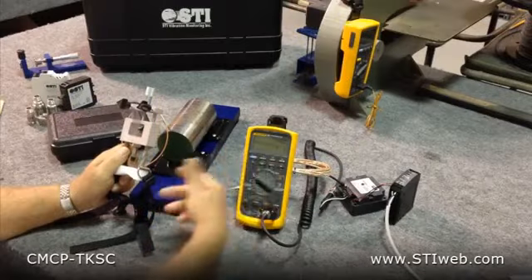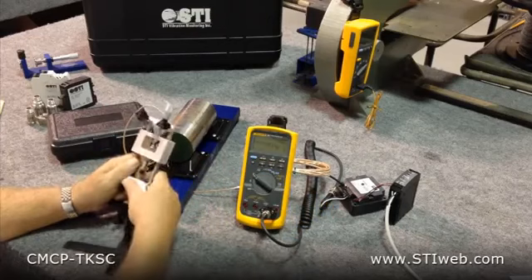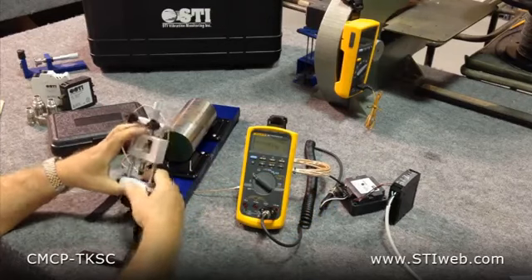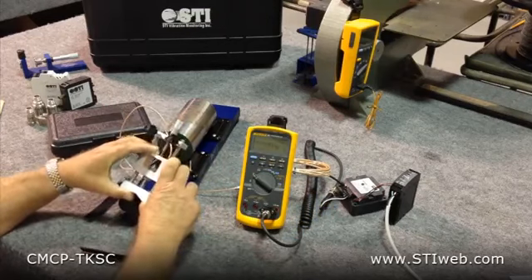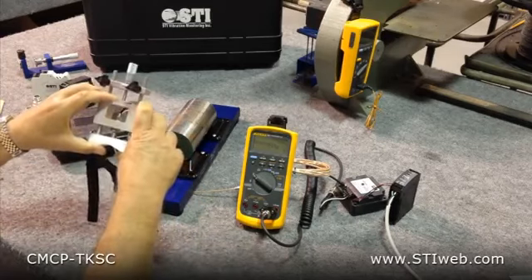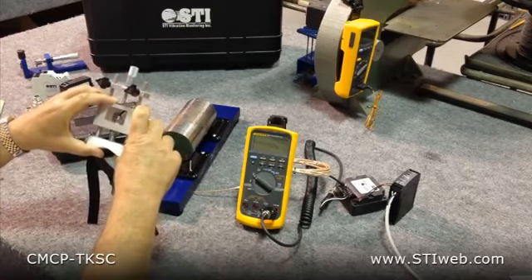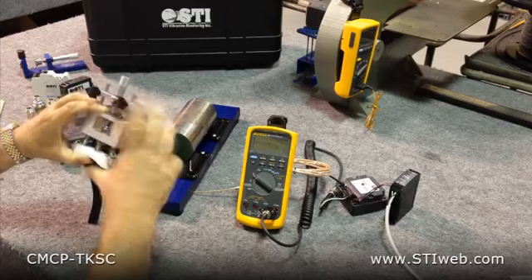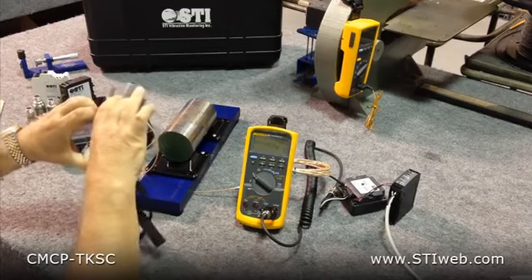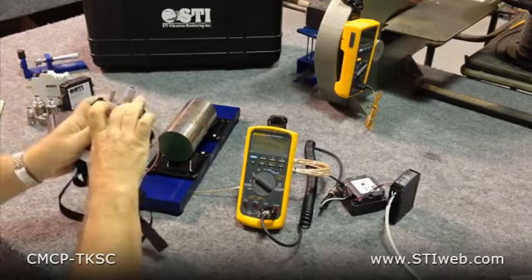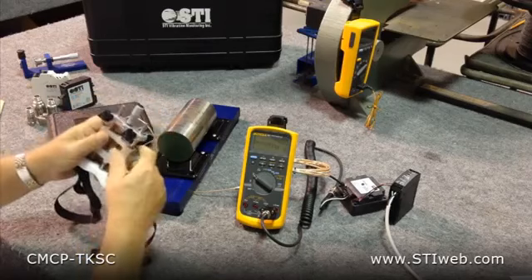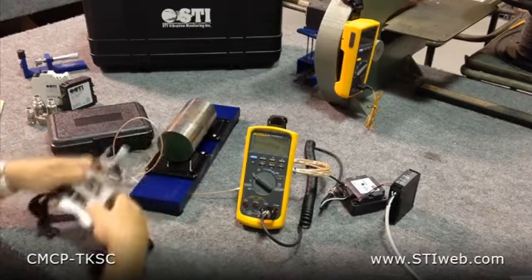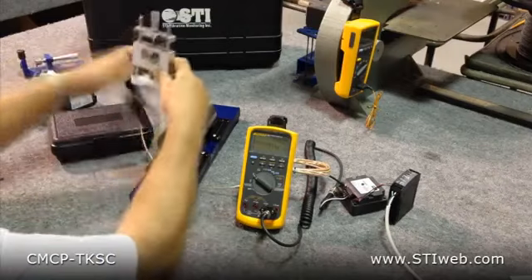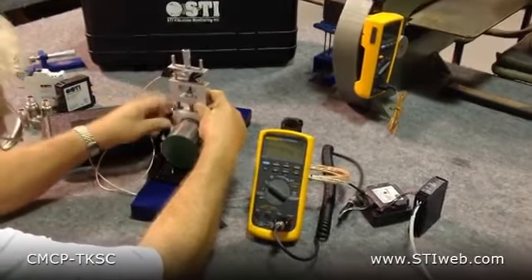So anyway, I'm not going to go through the wiring setup, but we'll go through this. What I do is mount the proximity probe in the armature, making sure that the probe will stick out below the nylon. In other words, it'll actually touch the surface of the shaft. Adjust the top plate to hold it there temporarily. Then we get it mounted on the shaft by using the webbing that we provide.